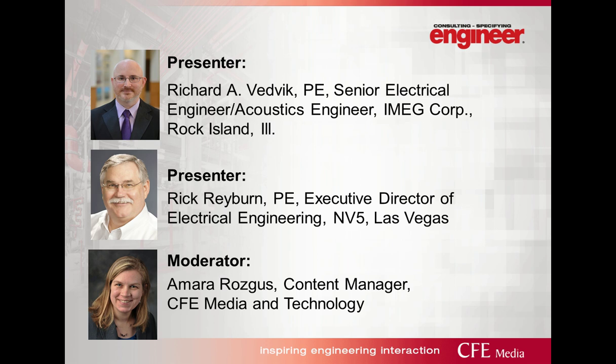You're going to have to take into consideration what your ground fault sensor trips are going to be set at. And unfortunately, in most applications, you're going to find that they're going to be higher than you would like them to be. However, we also have ground fault coordination. So as you're taking a look at your coordination settings, you're going to be doing that for ground fault as well. One last question was whether or not flywheels are considered emergency sources in the U.S.